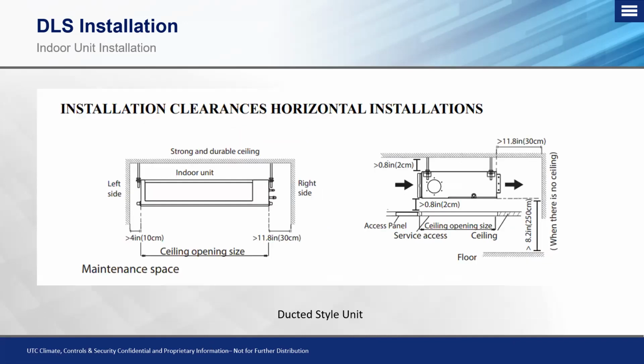Now, when we deal with our ducted style applications, we first want to make sure that the unit is actually supported properly and hung properly. So you can see up here, we have our little arms that hang off of the unit itself, followed by our all thread, and our locking nuts. Now this can be supported either to a direct structure, or we can use unistrut to help suspend this unit. And then we need to make sure that we put our level on top of the unit and make sure the unit is level and not sitting too far left or too far right.